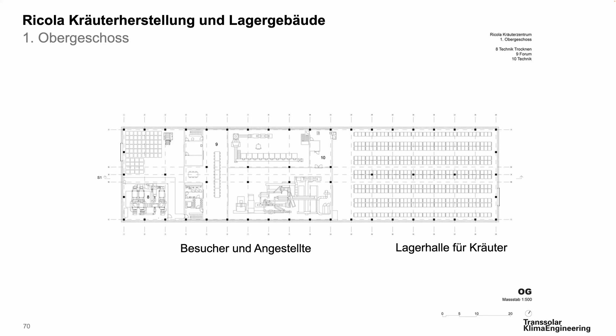We then looked at the humidity levels. They only want to keep the storage space at 10 degrees, but what they don't want is large swings of relative humidity, because that kills the herbs. Looking into the code for thermal insulation, you need a U-value, U-wert, of 0.5 watts per square meter Kelvin. That would mean a sandwich panel of insulated steel with no humidity absorption.